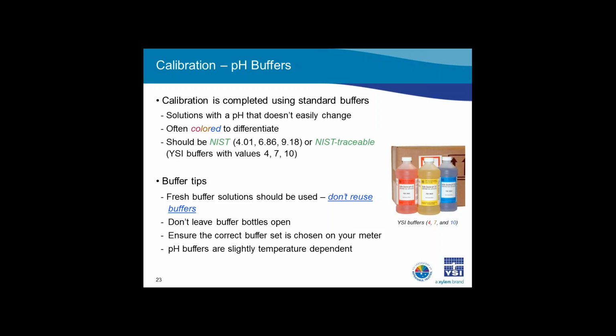Once you have acquired your buffers, check your instrument to see if you have an auto buffer recognition feature. If you have this feature, select the buffer set that matches your buffers. Some instruments, like the YSI TrueLab, have over 20 different buffer set values pre-programmed in the instrument. If you can't find your buffer set, I suggest you turn off auto buffer recognition so you don't introduce error by calibrating to the wrong value. For example, NIST and NIST traceable buffers have different values, as you can see in this slide.